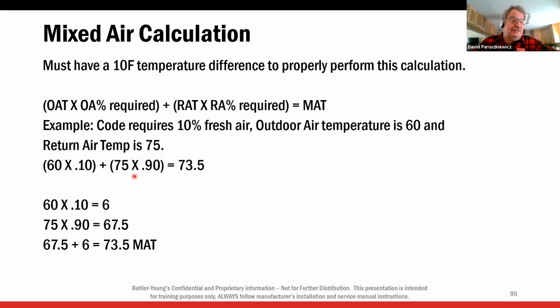of 75-degree air. So the 60 outdoor air temperature times 0.1, 10%, is 6. The 75 return temperature times 0.9, or 90%, is 67.5. Add the two together, and my mixed air temperature is 73.5. That is the temperature I should have in mixed air when my minimum position damper is set properly. Like I say, who's really going to do this? Well, this is how you actually do it.